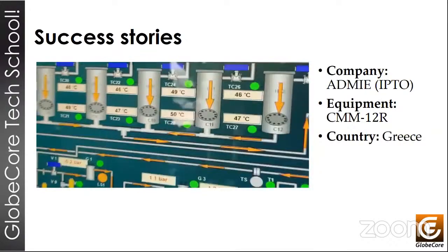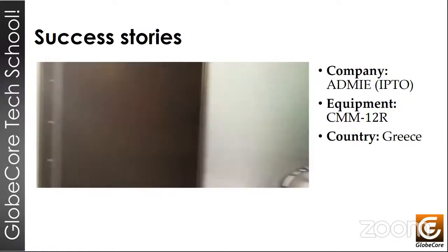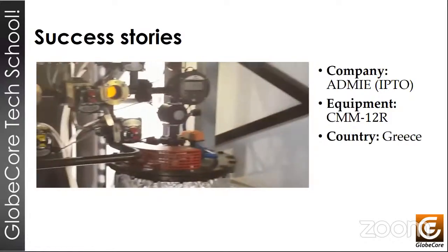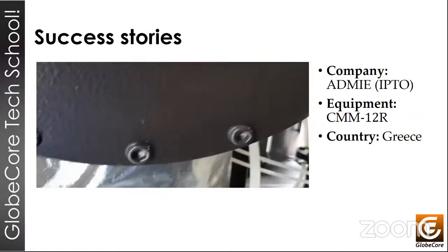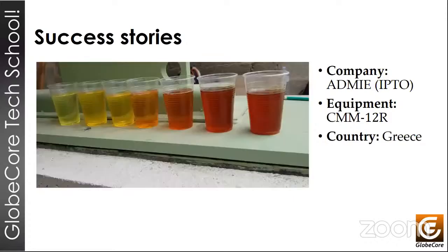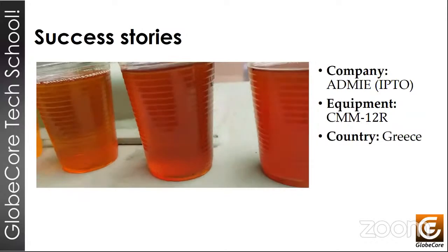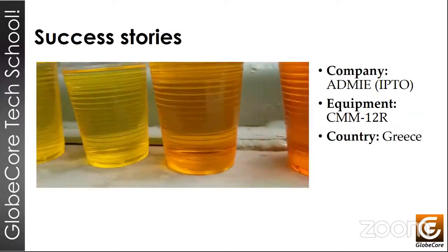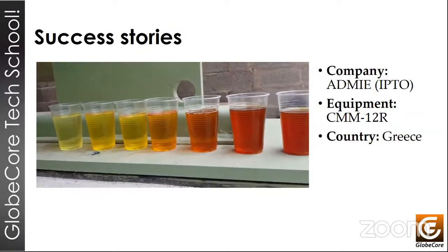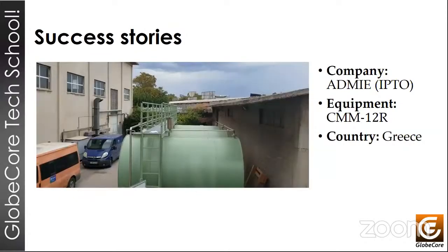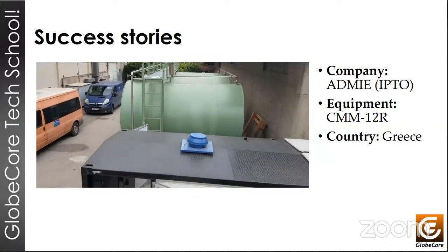The operator controlled the reactivation process, for example, absolutely remotely. And after reactivation, the sorbent was again used for regeneration without the need to load and unload the sorbent. And this property allows the sorbent to be reactivated around 300 times or so. It does depend on the quality of oil, obviously. If we use the sorbent with really bad oil all the time, I guess the 300 times will go down a little bit, but it's a good baseline figure, 300 times.